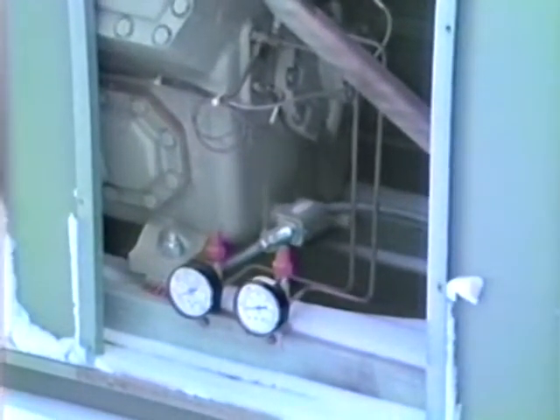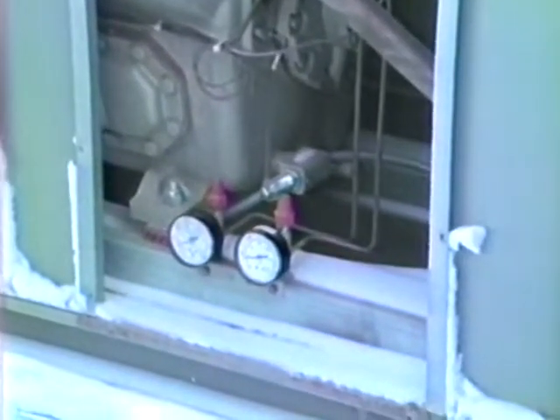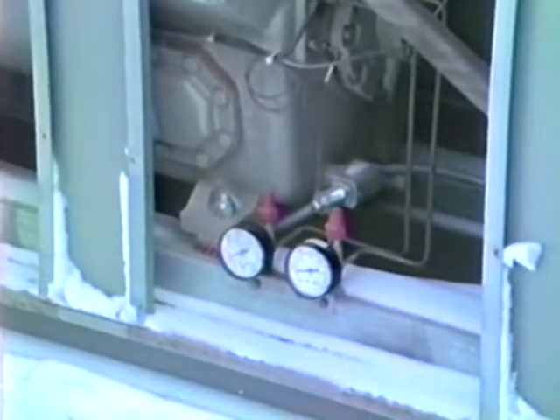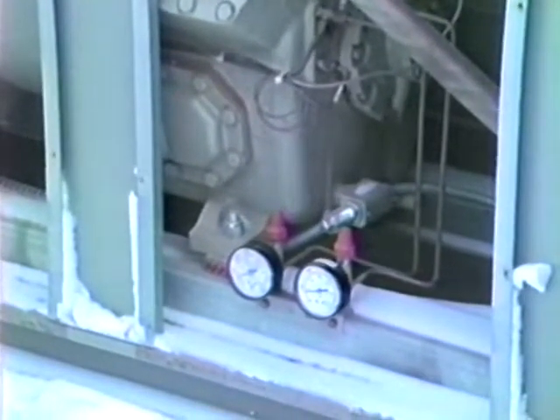The other end of the compressor has 2 other gauges. One on the right is the oil pressure. It should be somewhere around 20 pounds higher than the suction. The gauge on the left of the oil pressure is a discharge gauge, discharge pressure. That should be somewhere in the range of 250 to 300 pounds in normal operation.